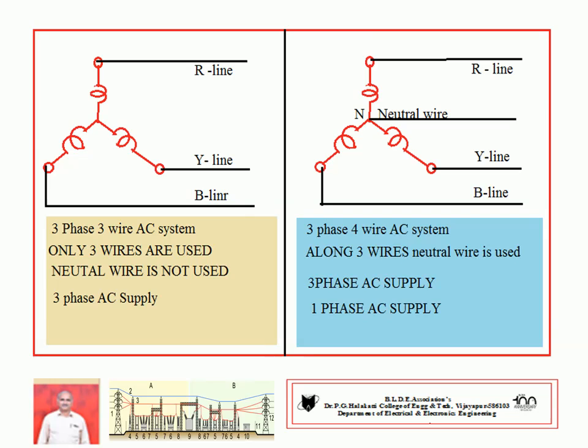On the other hand, if the neutral wire is not taken for further connections, such an AC system is referred to as a three-phase, three-wire system. As per the consumer's point of view, we use the second one, the three-phase, four-wire AC system. So, the secondary of the distribution transformer is a three-phase, four-wire system, because the consumers may use single phase AC supply, or the consumers may use three-phase AC supply.